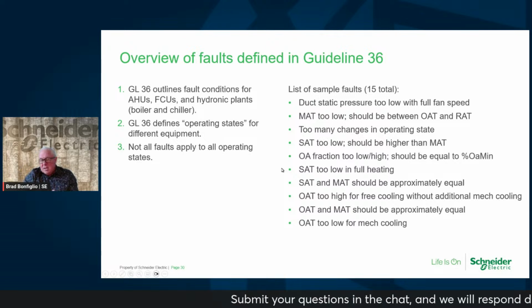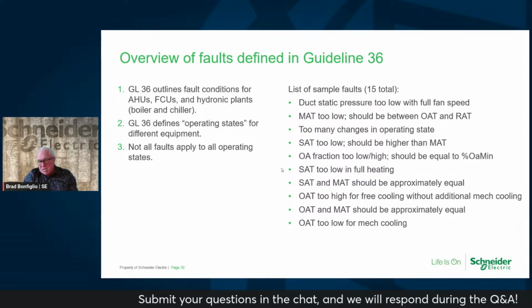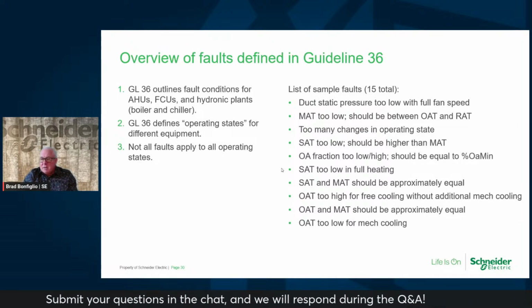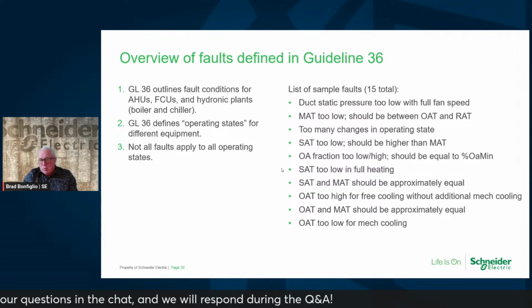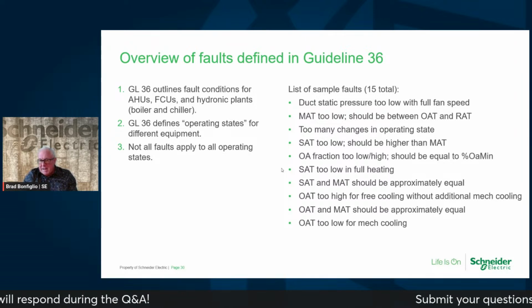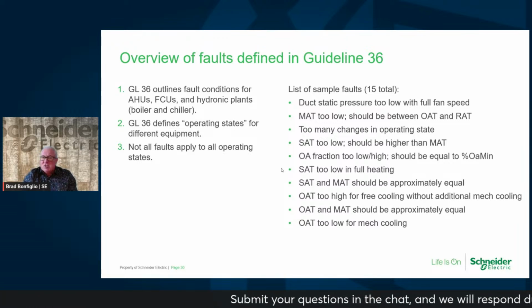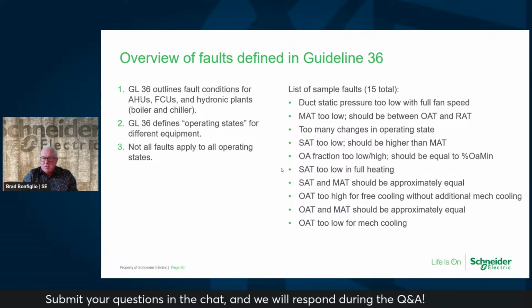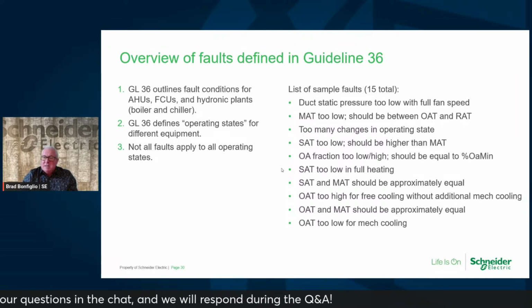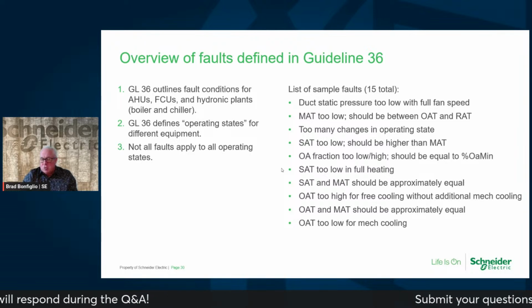Now, it doesn't mean you have to use Guideline 36 faults. There are third-party, cloud-based, premise-based systems out there that'll also pull data points out of your BMS to do fault detection. I like the fact that these were built into Guideline 36. That way, if you follow the standards as a manufacturer, this means that at the start of the job, you actually can get these faults in your project.